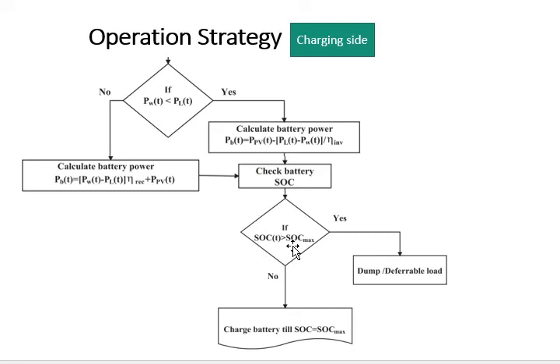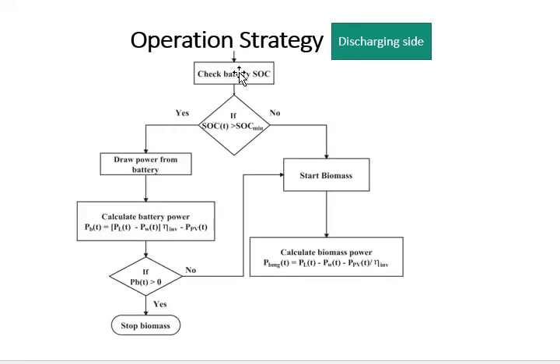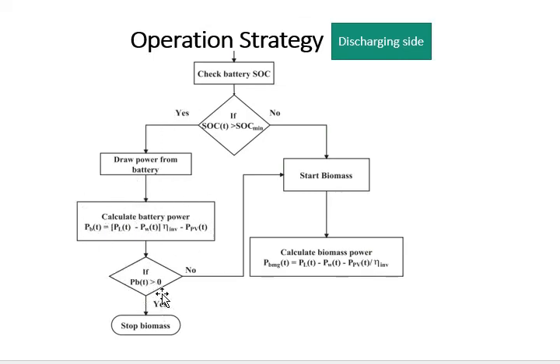On the discharging side, if solar and wind power are inadequate and batteries are also not able to produce the desired power to meet the load demand, then the biomass gasifier supplies power to the load. However, if the batteries have sufficient capacity to meet the deficient load, energy will be taken from the batteries. If at any stage the battery SOC is below the threshold and the gasifier has sufficient surplus power, the battery will be charged from the gasifier.